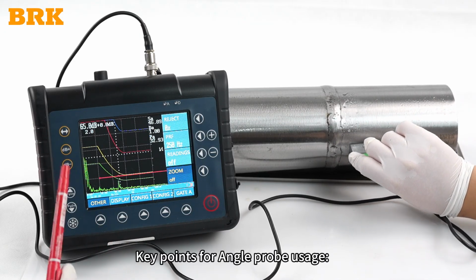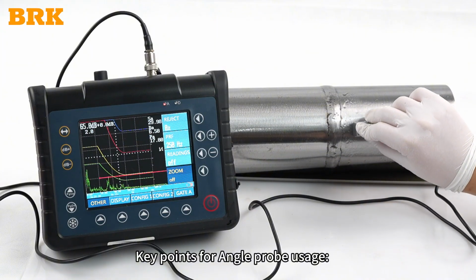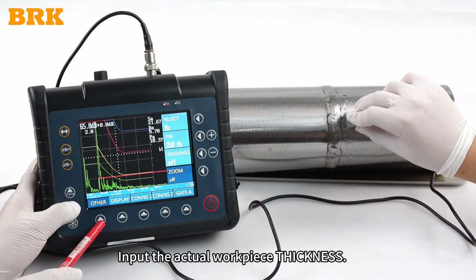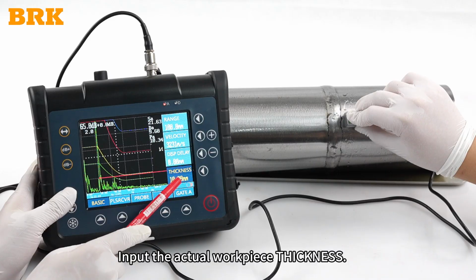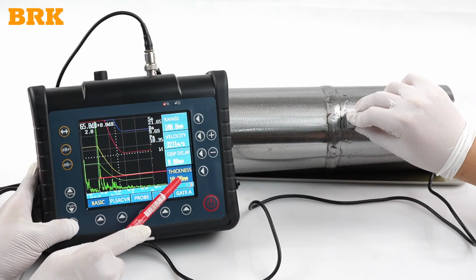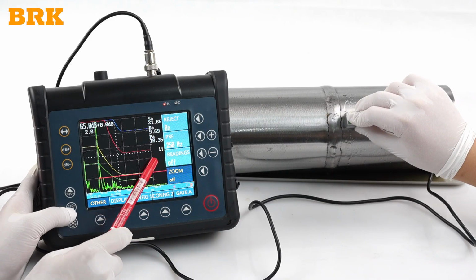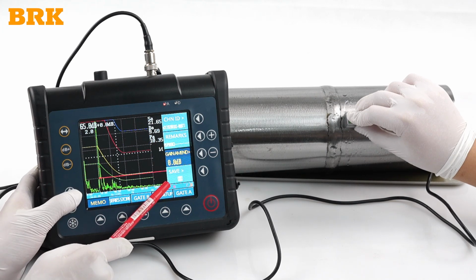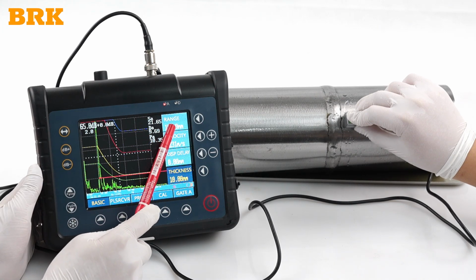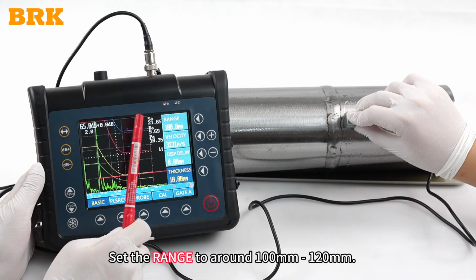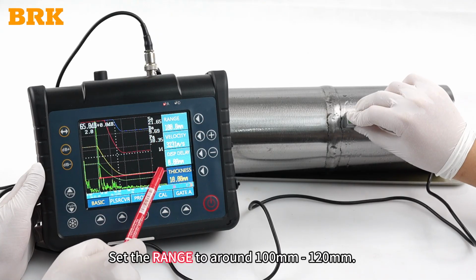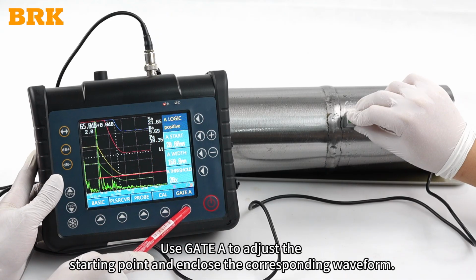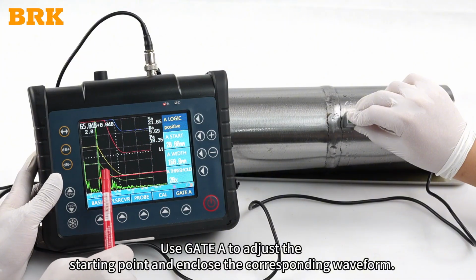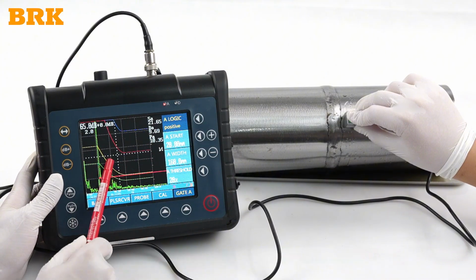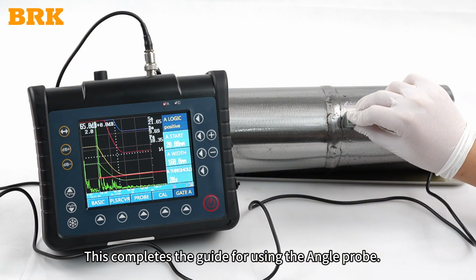Key points for angle probe usage. Input the actual workpiece thickness. Set the range to around 100 mm to 120 mm. Use gate A to adjust the starting point and enclose the corresponding waveform. This completes the guide for using the angle probe.